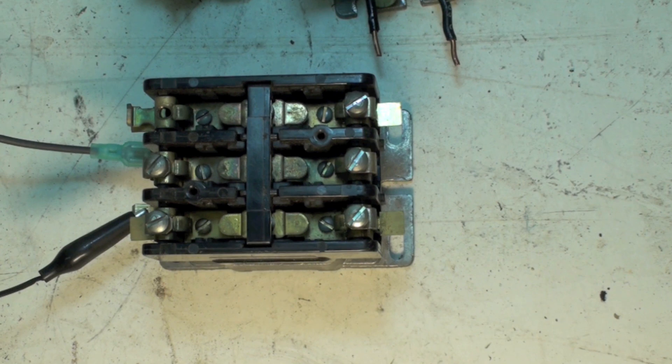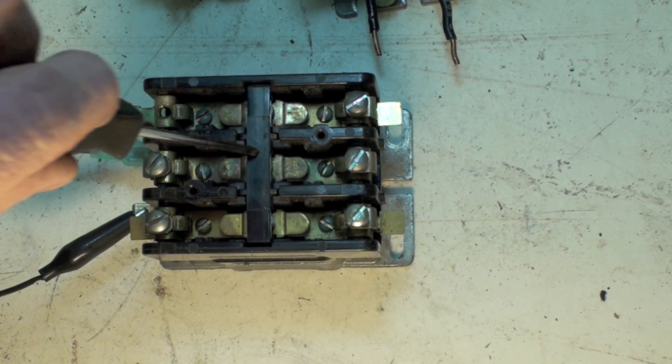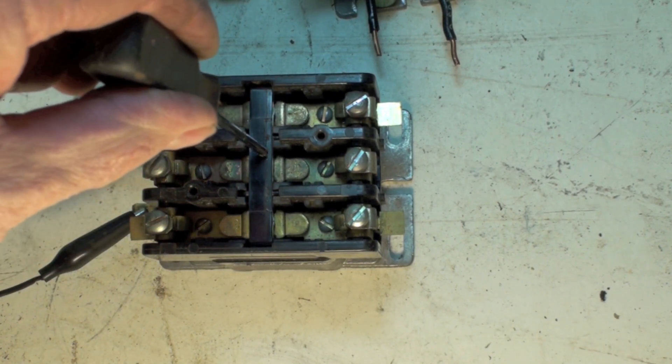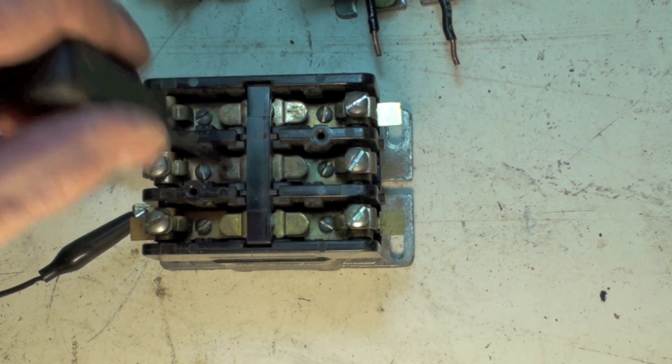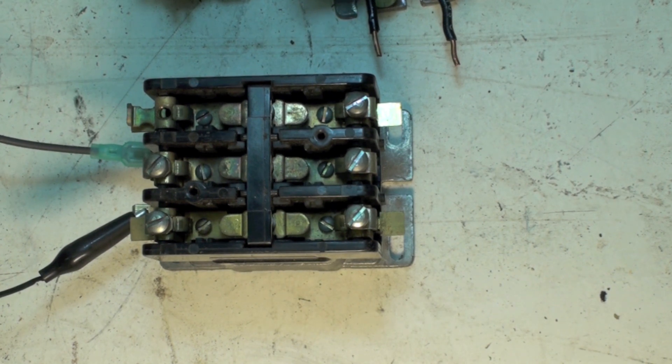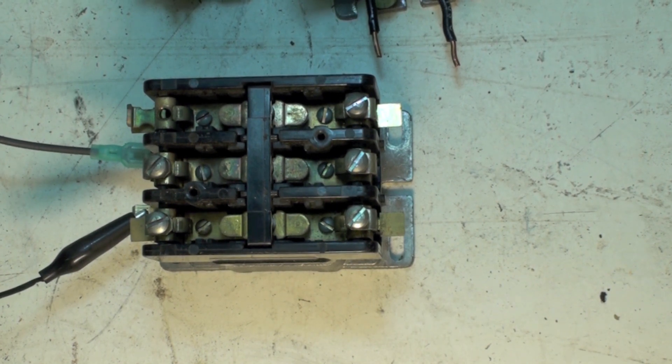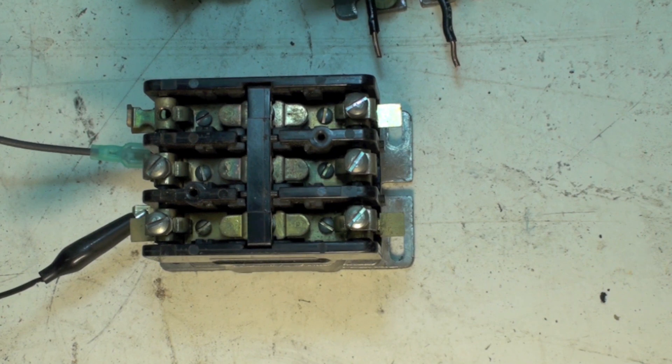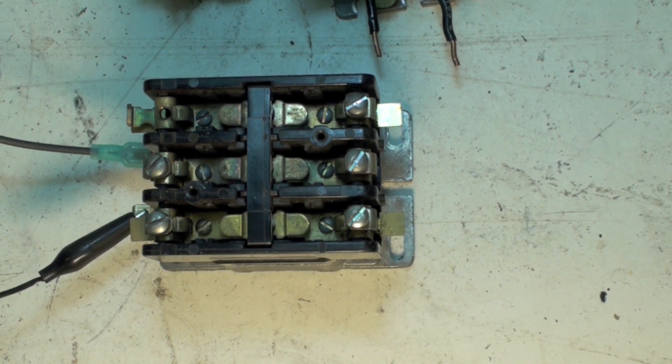Because every time this armature goes down, it's gonna make contact and it's gonna break, and it's gonna make and break and make and break. And usually takes out the contacts in just a short time. So the contactor almost always has to be replaced in that case, but it's usually not a contactor problem that caused it.